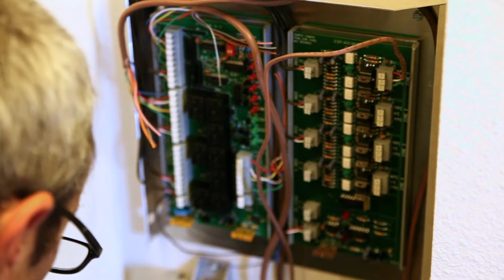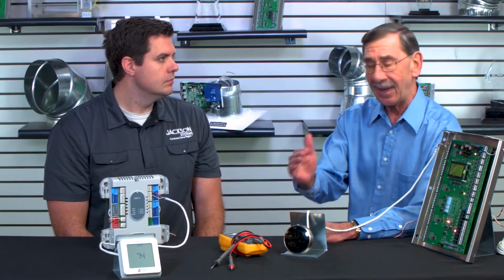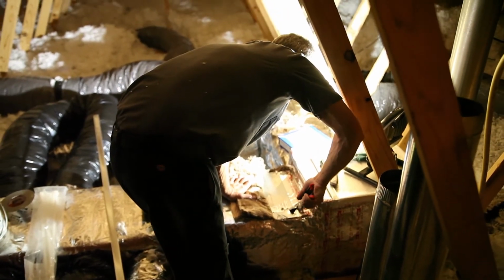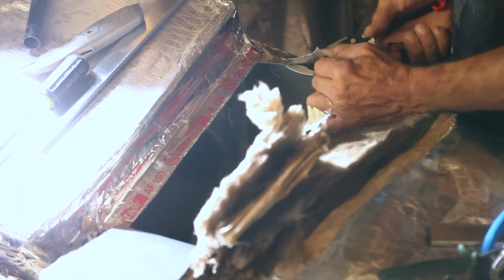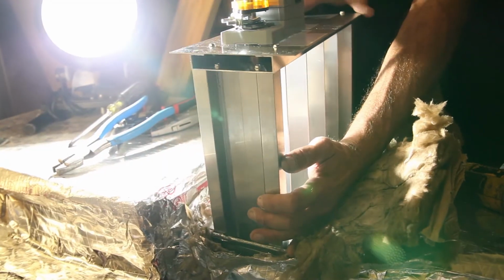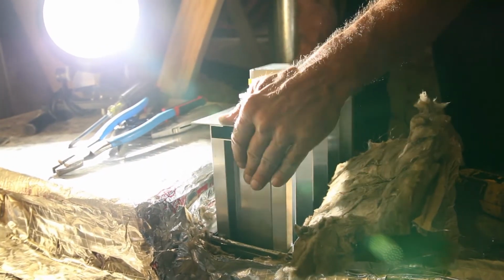The other important thing is running wire. Today it's easier because we have wireless thermostats, so in a two-story home I wouldn't necessarily have to run additional thermostat wire upstairs - I could use a wireless thermostat to communicate back to a zoning panel that controls a damper. But accessing the ductwork is important, because if I can't get a damper in to control conditioned air into a space, or shut it off when satisfied, it's not going to work.